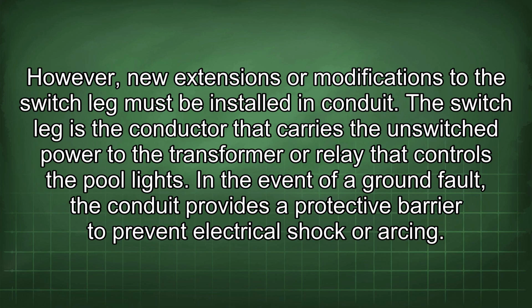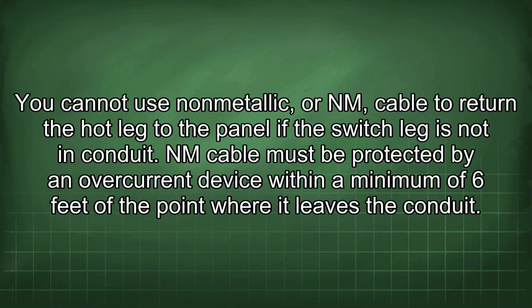The switch leg is the conductor that carries the unswitched power to the transformer or relay that controls the pool lights. In the event of a ground fault, the conduit provides a protective barrier to prevent electrical shock or arcing. You cannot use non-metallic or NM cable to return the hot leg to the panel if the switch leg is not in conduit. NM cable must be protected by an overcurrent device within a minimum of 6 feet of the point where it leaves the conduit.